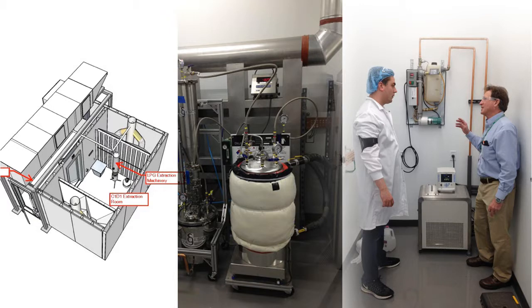In addition to that, we've engineered this room so there are no ignition sources, meaning there's no way that someone can create a spark, either static or by any electrical equipment. All the electrical equipment in the room is National Electrical Code Class 1, Division 1, Group D explosion-proof equipment. And we minimize the electrics because that type of equipment is very expensive. So we try to use air power, pneumatically operated equipment, and if something needs to be electrically powered, we can have it operated in an adjacent room. We call that the ante room. And then, for instance, for a heater or a chiller, we can bring the chilled water line in or the heated water line in to help operate the equipment. But again, we make an exceptionally safe environment for the operation of that type of facility.